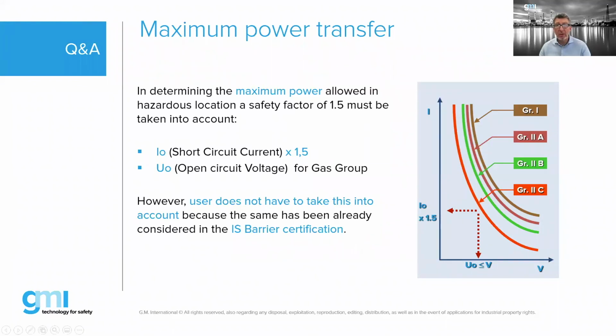So those are the curves for different gas groups. They're not the actual curves, they're a replication of the same. So there's a maximum voltage and a maximum current that you can use in gas group IIB, IIC, IIA, and so forth. And given a constant voltage, you need to be below the curve for the current. But the current is not the current stated, but the current stated under fault condition multiplied by 1.5. But as I mentioned here, the short circuit current is taken into account by the manufacturer. So if we tell you it's certified for group IIC, well, then it's certified for group IIC.